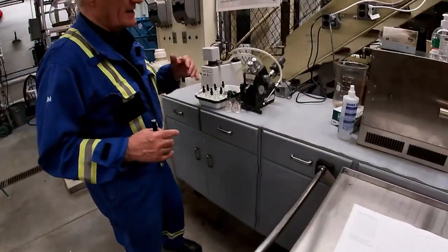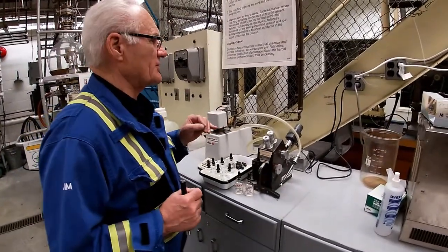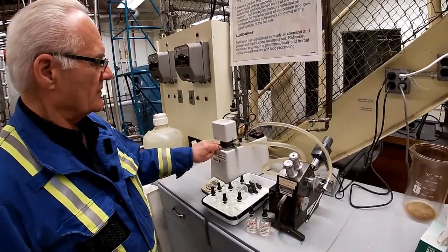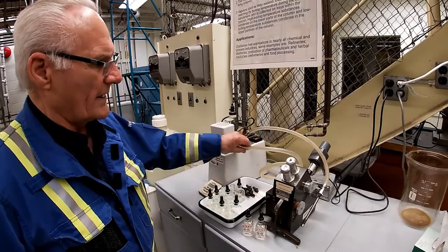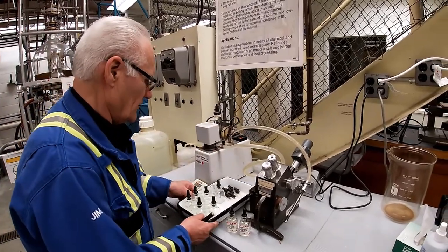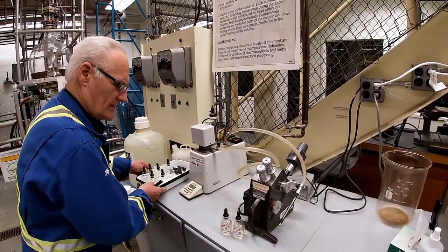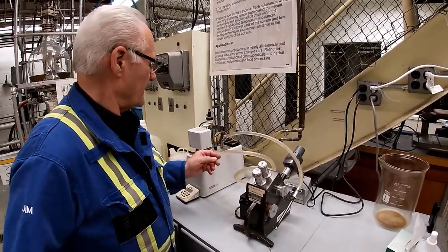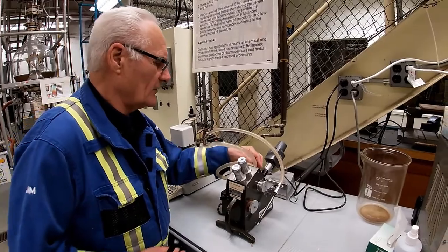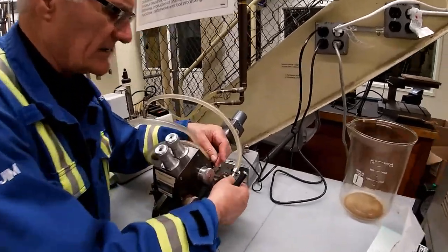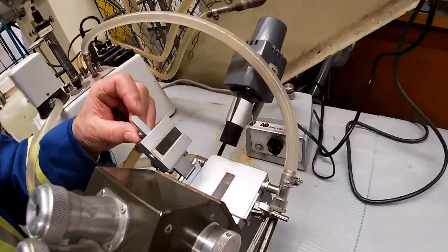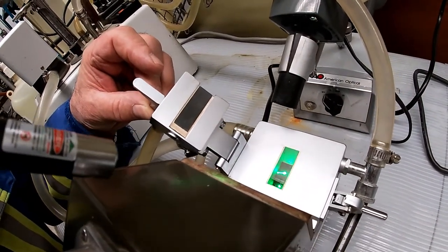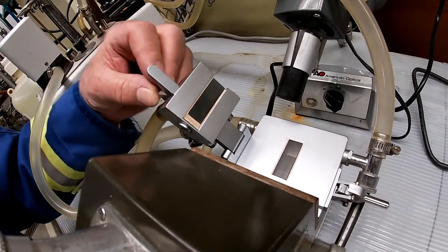The refractometer requires a very constant temperature. So there's a temperature bath sitting here, which is going to control the temperature of the water coming off. I'll just move these out of the way. Water is going to be pumped out of here into the refractometer, and I don't know how easily you can see this, but if I open this up, there's our prism and the actual light source itself in there.